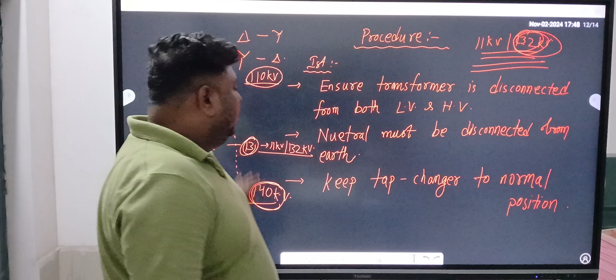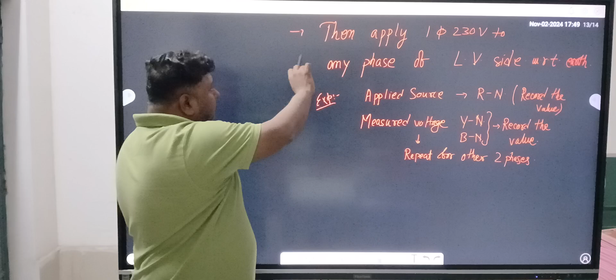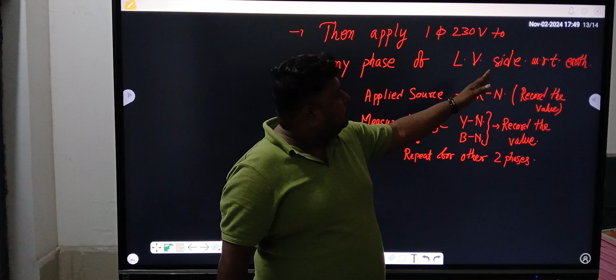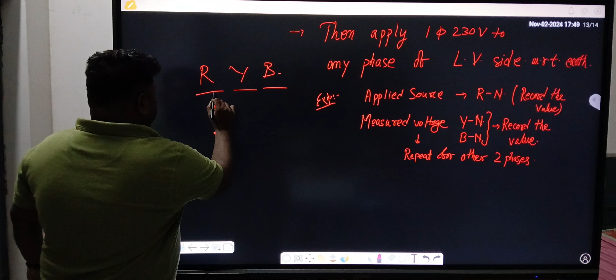Apply single phase 230 volt supply to any phase on the LV side with respect to earth. Again repeating: apply single phase 230 volt to any phase of the LV side with respect to earth. That means we are going to give a single phase supply to any one phase. We know three phases exist in the transformer: R, Y, B. So to any one of them we are going to give the source voltage through an external single phase supply.